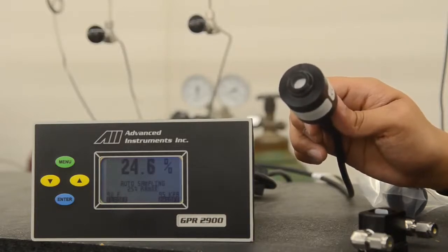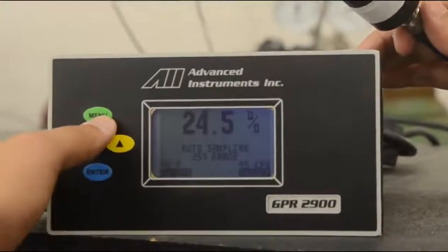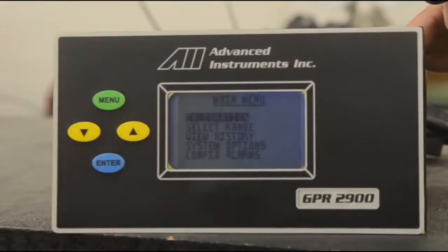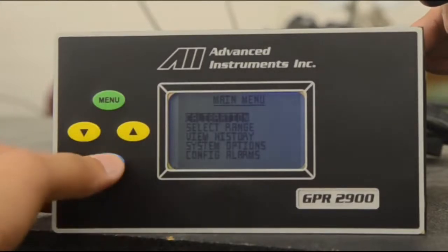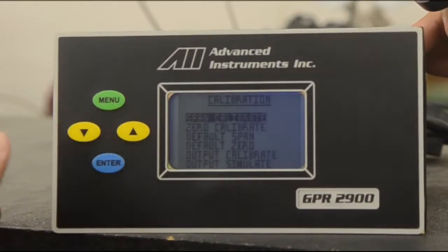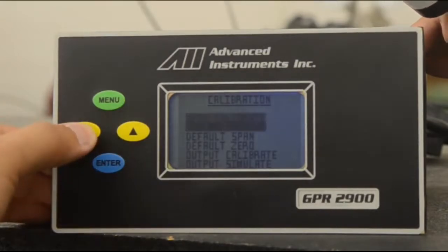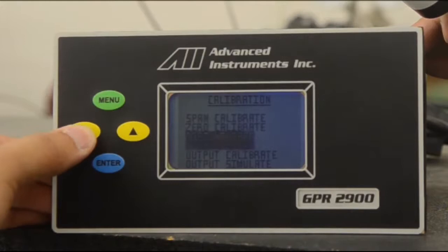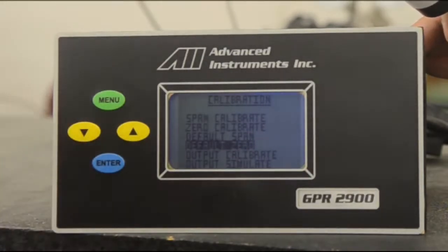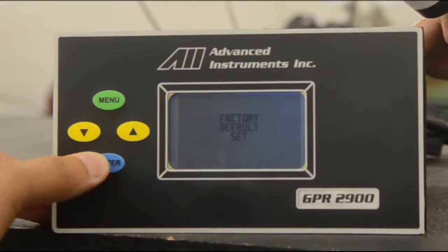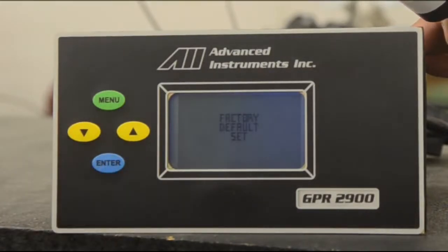Now, to perform our calibration, we hit the menu button, which will take us to the main menu of the analyzer. Calibration is already highlighted, and you can hit enter to go to the calibration menu. Now, when you first do a sensor installation, it is recommended to perform a default span and a default 0. When you're at default 0, press enter, and you see factory default set.